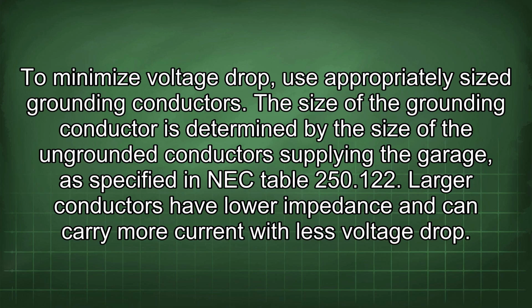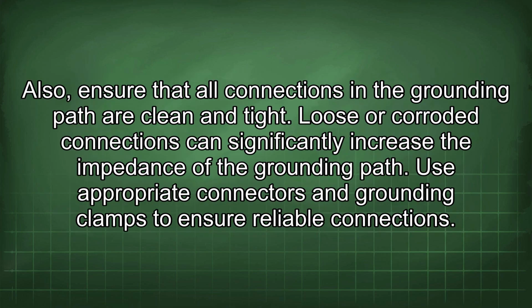The size of the grounding conductor is determined by the size of the ungrounded conductors supplying the garage, as specified in NEC Table 250.122. Larger conductors have lower impedance and can carry more current with less voltage drop. Also, ensure that all connections in the grounding path are clean and tight. Loose or corroded connections can significantly increase the impedance of the grounding path. Use appropriate connectors and grounding clamps to ensure reliable connections.